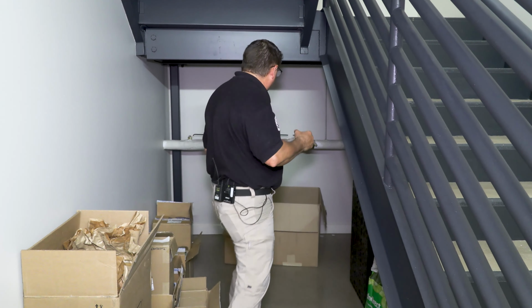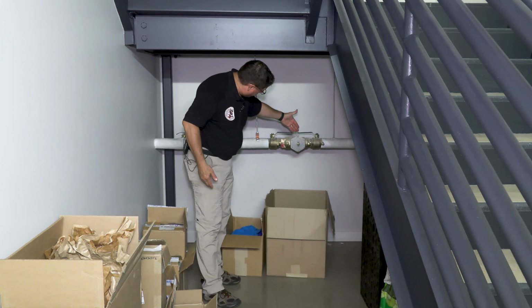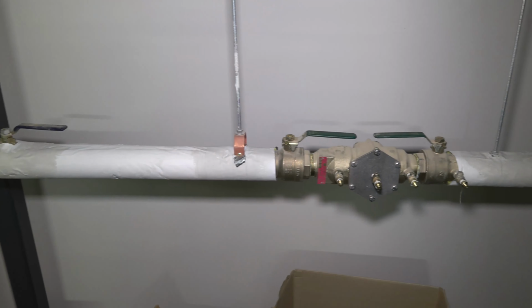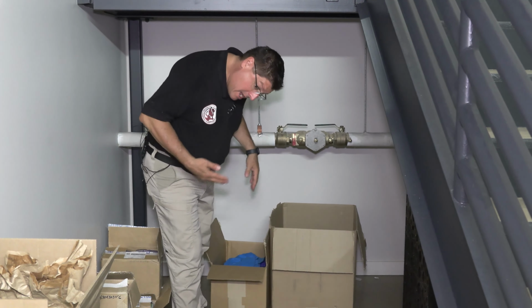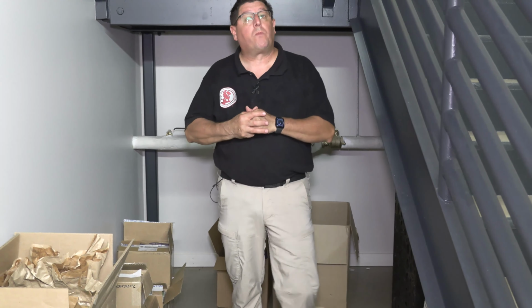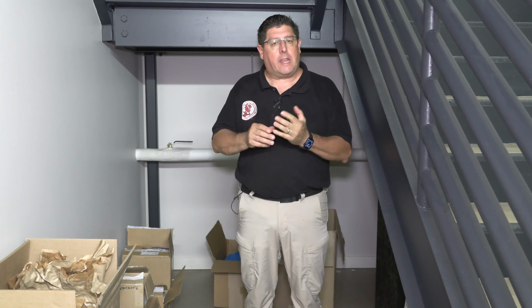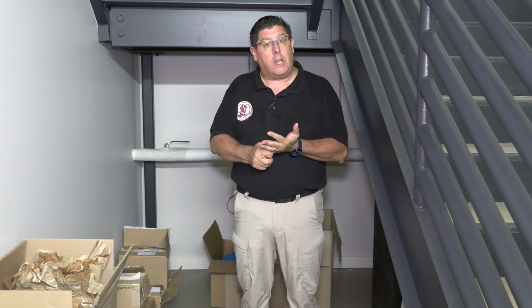In this particular building, this is our backflow preventer right here. The water supply passes through it. We have a shutoff on this side, a shutoff on this side, and then it migrates into the other room. So when you do your plumbing inspection, you need to trace all the potable piping to make sure that, again, we don't have issues of backflow prevention, things like cross-contamination, etc. So let's go trace the plumbing.